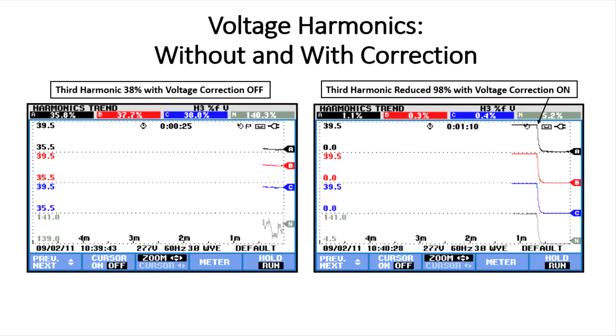We can see what the actual total harmonic distortion, or the distortion for a particular harmonic, was shown on the graph on the left with the machine operating as it was, and on the right with the voltage correction engaged. And you'll see that the harmonics dropped about 98% simply by turning the disconnect on to the voltage correction system. And we've actually captured on the right-hand graph what it was as we turned the disconnect on. It instantly reduced to less than approximately 1% and stayed there.